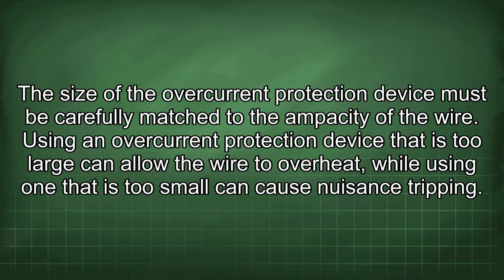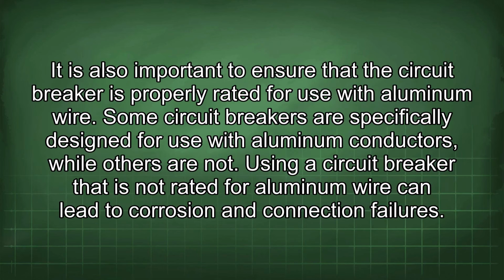Using an overcurrent protection device that is too large can allow the wire to overheat, while using one that is too small can cause nuisance tripping. It is also important to ensure that the circuit breaker is properly rated for use with aluminum wire. Some circuit breakers are specifically designed for use with aluminum conductors, while others are not. Using a circuit breaker that is not rated for aluminum wire can lead to corrosion and connection failures.